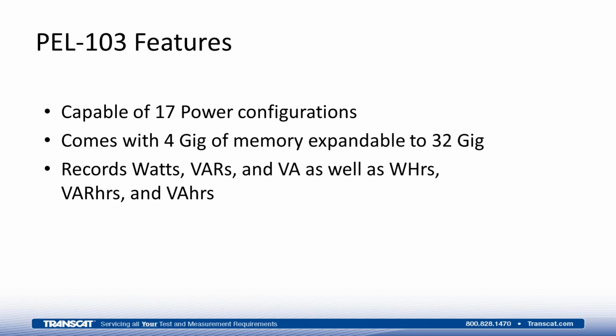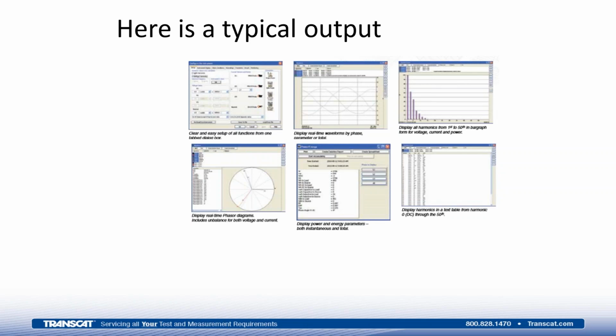We incorporate memory in these units, expandable up to 32 gig in the case of the PEL. So this thing could actually record for months and months before downloading. It also incorporates communication capabilities, Ethernet and Bluetooth, to transfer the data either real time or after the recording is done. And it's quite common to record watts, vars, and VA, as well as the watt hours, the var hours, and the VA hours of a load. And you would then generate a graphical result of that data.